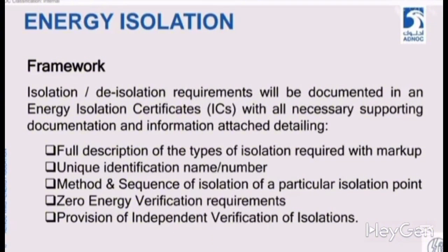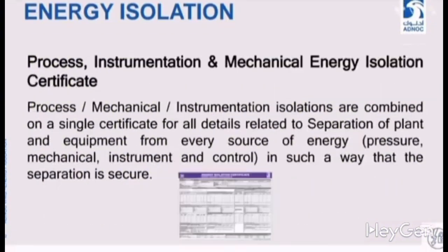The energy isolation certificate is the first certificate. We will have a process instrumentation and mechanical energy certificate. All types of equipment, any energy isolation will be taken, insured and confirmed on a single certificate. Process mechanical instrumentation isolation is combined on a single certificate. All three are combined on the same certificate for all details related to the separation of plant and equipment from every source of energy. According to these, any pressure source we have will be pressured and its update will be taken on a single certificate.